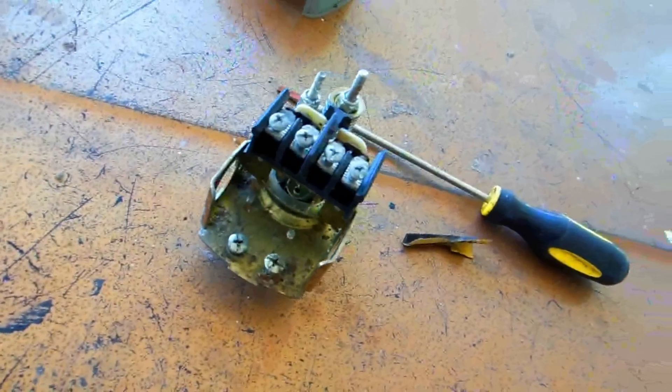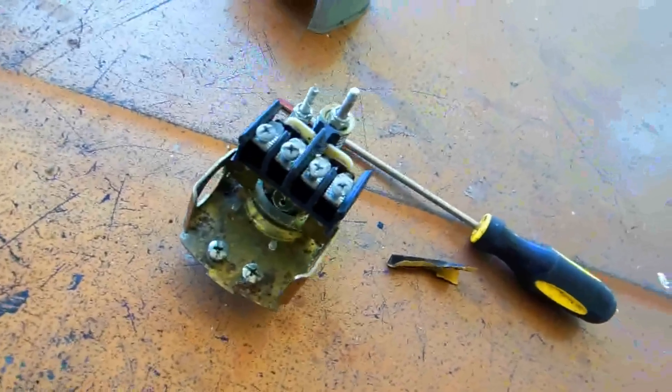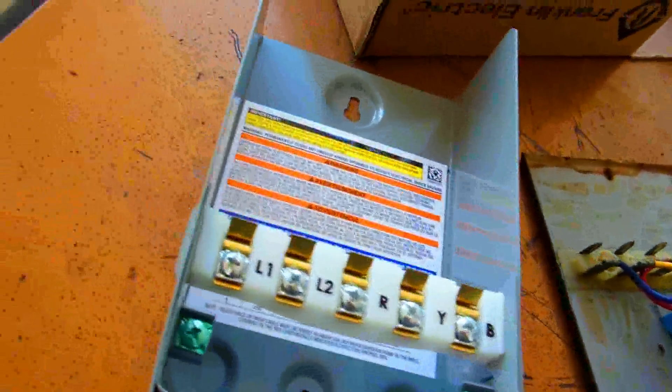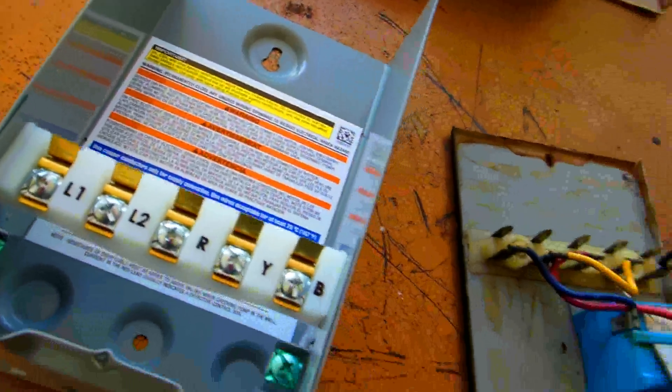This one is a three-wire 230-volt half-horse — not a really big one. This is the control box. This happened to be my problem. I was lucky, so the motor to pump didn't have to be pulled.